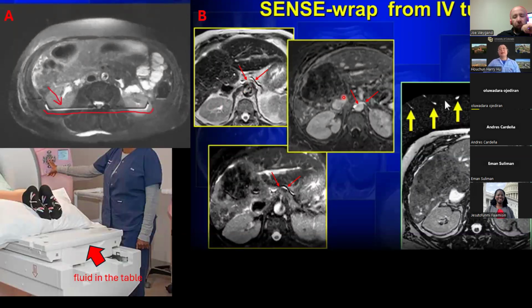This very thin line here in the blue background, I got from one of the ISMRM talks. This thin line is actually an artifact. It's nearly impossible to see, but it ends up being, again, IV lines wrapping in, and often the coil sensitivity profiles don't pick up these IV lines. The coil actually might be sitting underneath the IV lines and the anatomy, so you never get to see them. So it's often good to think about where signal on the outside of the field of view may accidentally wrap in without you even knowing it.